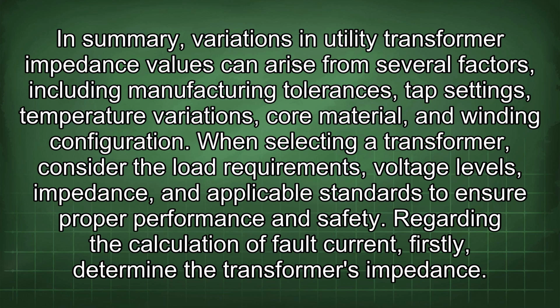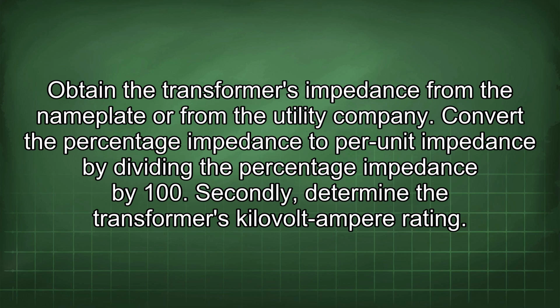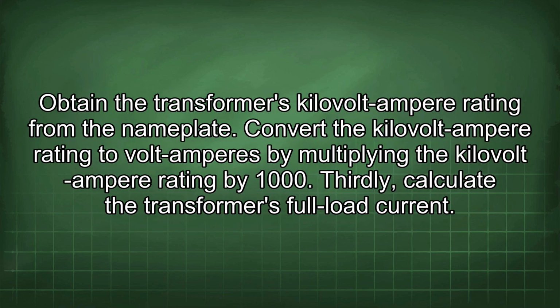Regarding the calculation of fault current, firstly determine the transformer's impedance. Obtain the transformer's impedance from the nameplate or from the utility company. Convert the percentage impedance to per unit impedance by dividing the percentage impedance by 100. Secondly, determine the transformer's kilovolt-ampere rating. Obtain the transformer's kilovolt-ampere rating from the nameplate.